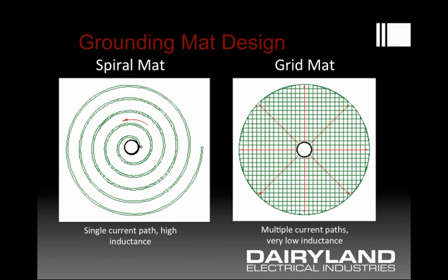Here's an example of the grounding mat designs. On the left, any single-conductor system can only have current flow down that conductor path — an ever-increasing length from the point of attachment to the pipe. With a gridded design, current flows in all directions away from the pipe, and as current flows outward there are more and more interconnected paths, resulting in lower and lower inductance. The voltage drops off with increasing distance in a gridded mat, giving the best performance and lowest voltage at the edge. With a spiral or single-wire mat, there will be a very high voltage at the edge, which is not desirable.